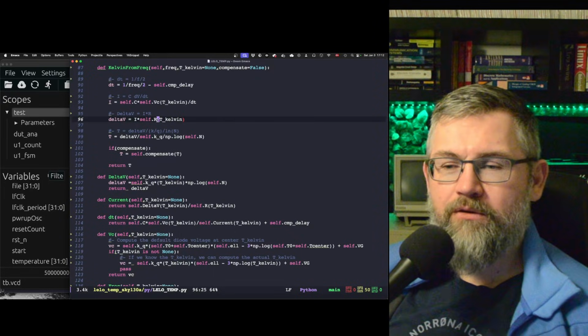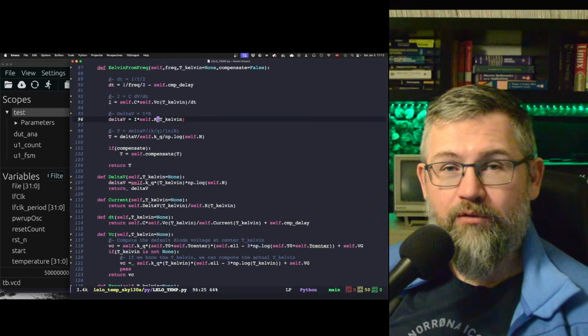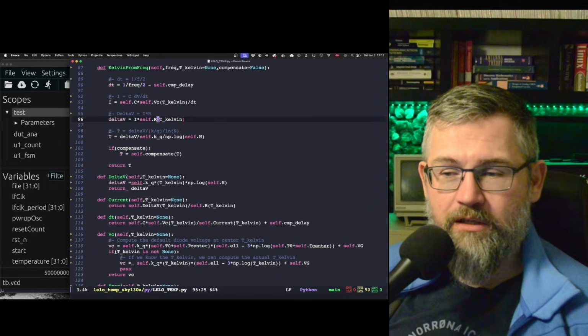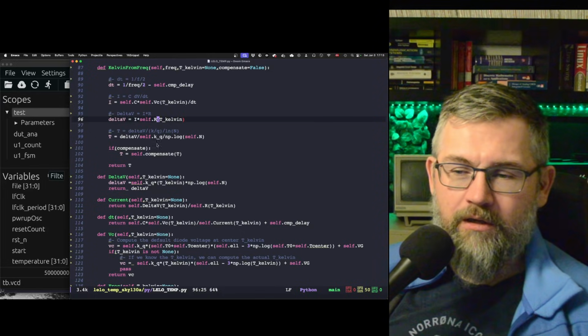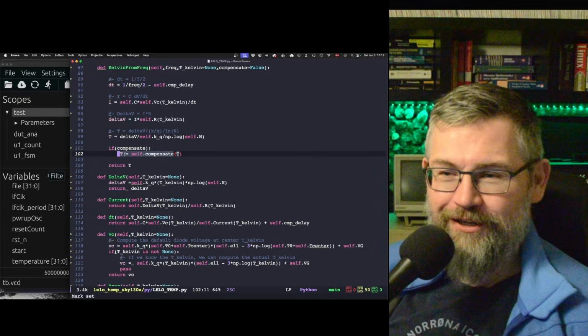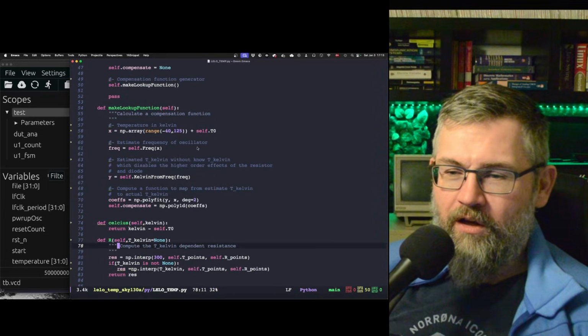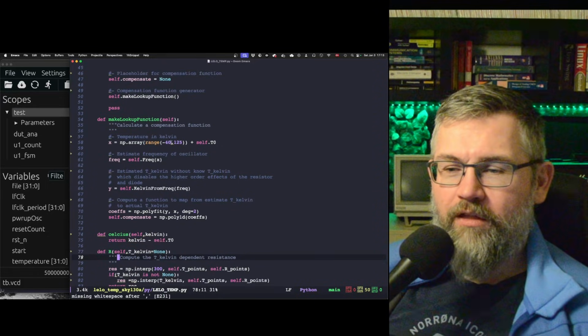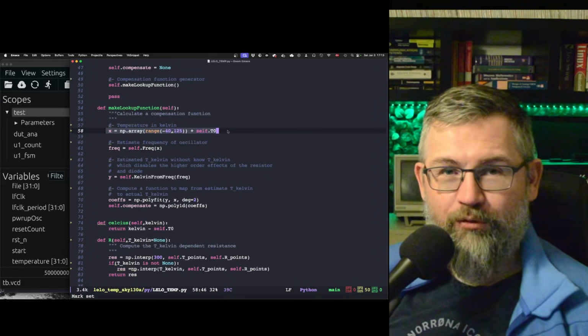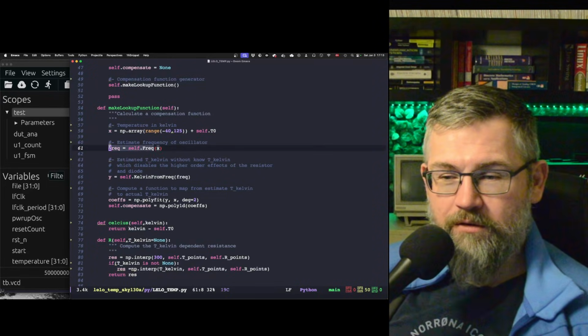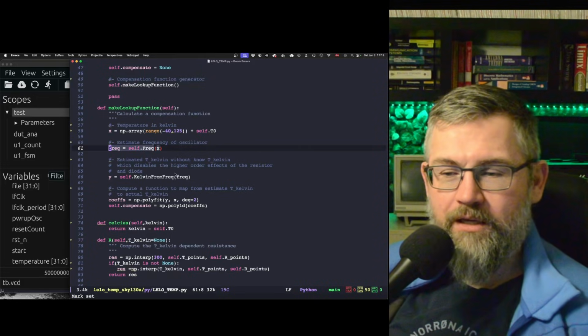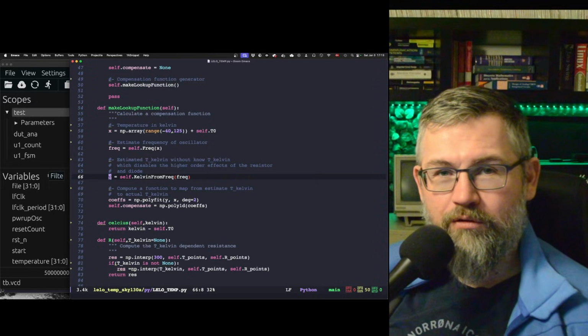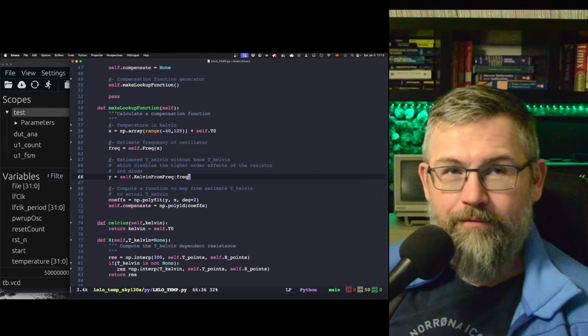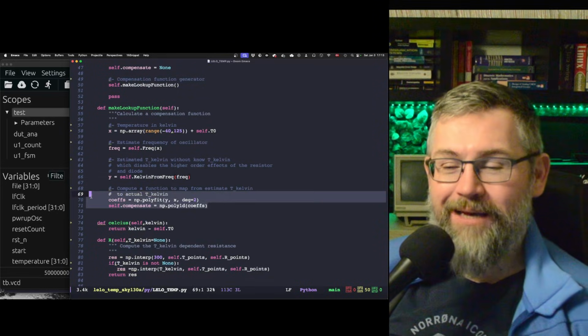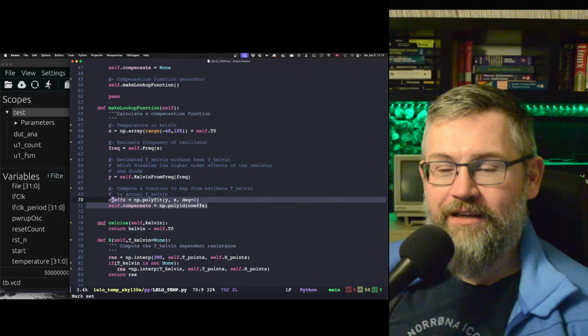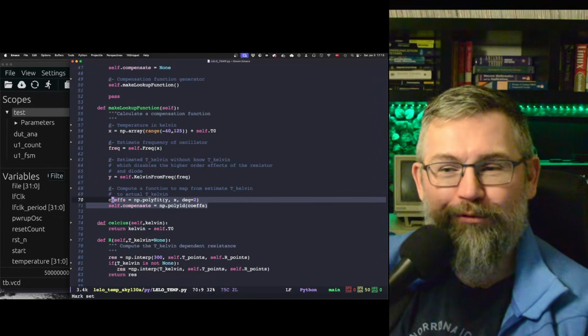But it turns out that most of those factors will either turn into an offset or a gain error—in some cases they actually turn into nonlinearity. What we can do for typical devices is run a compensation function, because since I know the physics of how this oscillator should work, I can generate a temperature range, calculate what the oscillator frequency should be, and then back-calculate what an estimated temperature could be if I didn't know the true temperature. Then I can make a second order polynomial to go from the estimated temperature to the probable true temperature.